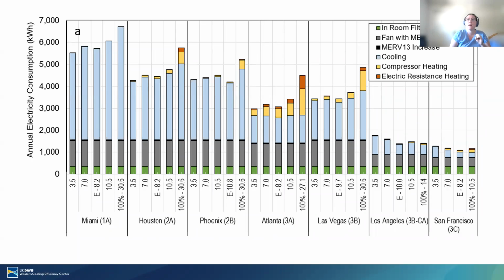But anyway, you can see basically what happens somewhere like Miami, right? As we increase outdoor air rate, our cooling energy use just goes up. And I don't show it here, but when we get to 100% outdoor air in most of these climates, we're actually unable to meet the cooling load with typically sized HVAC equipment. And then we have all these hours that don't meet the thermostat set points, which is just not going to work in the long run. So basically we're just analyzing here.